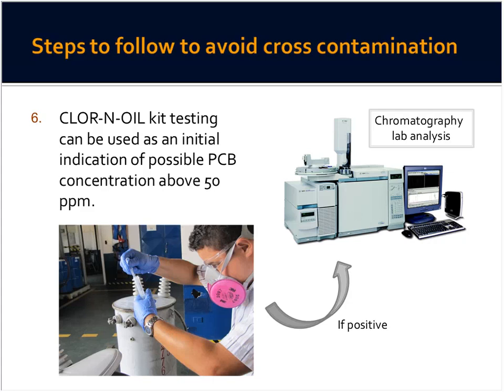Now, with the kit, we must remember a few things that have been experiences or lessons learned over the past few years with respect to the use of the kit. The kit will not give you a false negative, which is very good. If you have a negative result, well, then this will tell you that you do not have oil contaminated above 50 parts per million of PCB. It doesn't tell you that the oil doesn't have PCB. It just tells you that the concentrations are below 50 parts per million. There are other kits that have different concentration limits, like 20, but what is most commonly used in the field is the above 50 parts per million, because in many countries, 50 parts per million is the lower limit for characterizing an oil to be contaminated or not with PCBs.